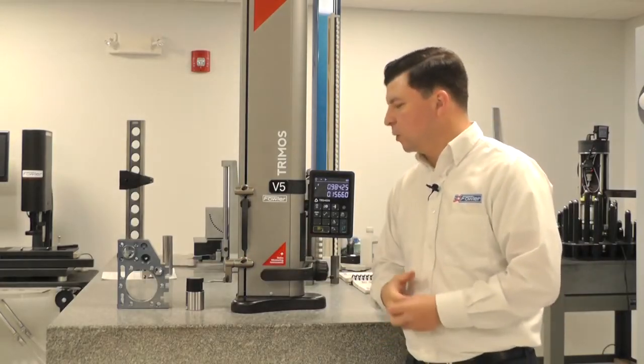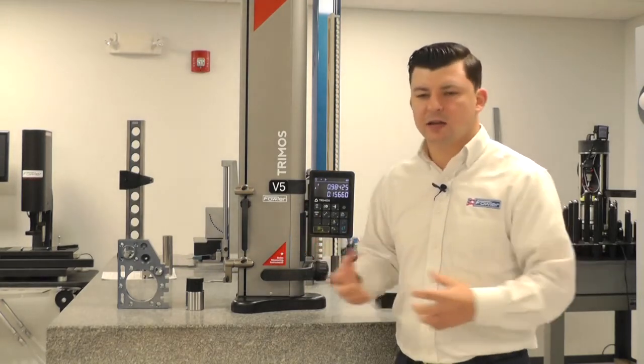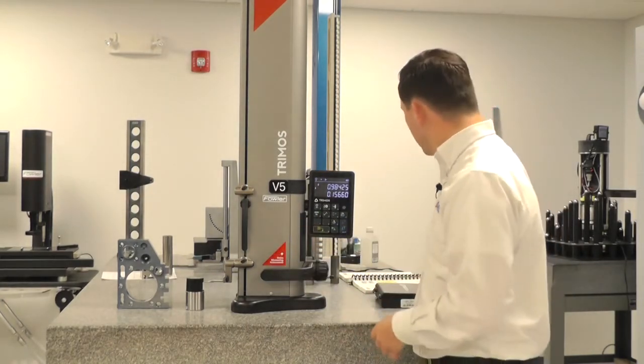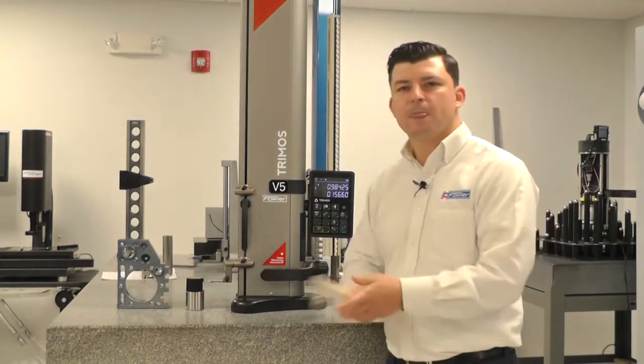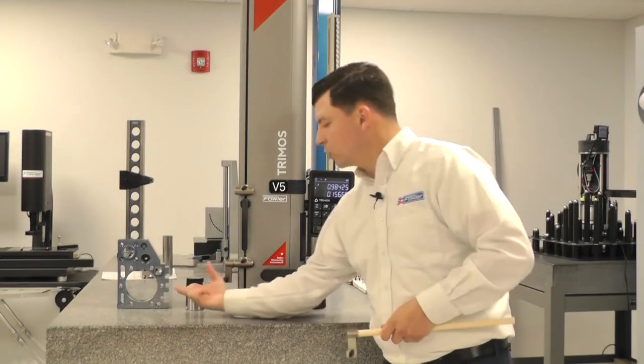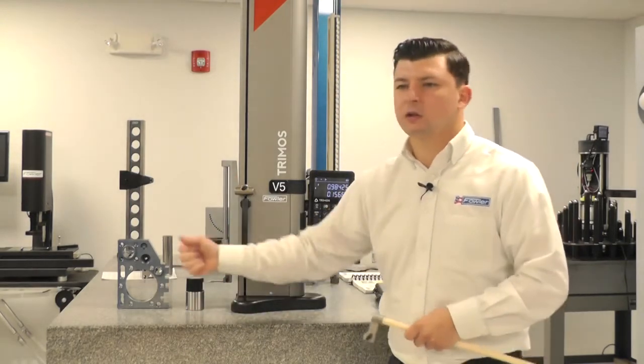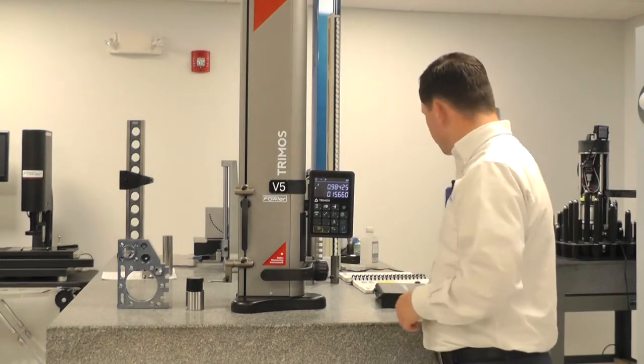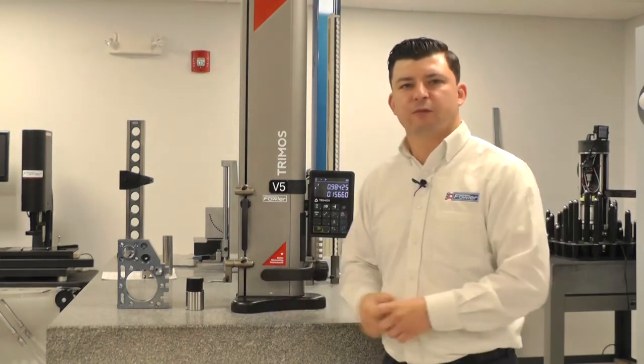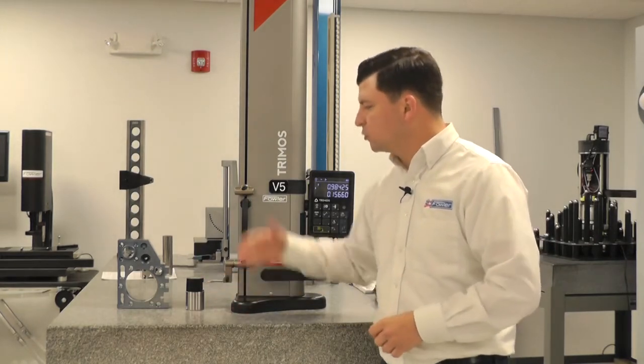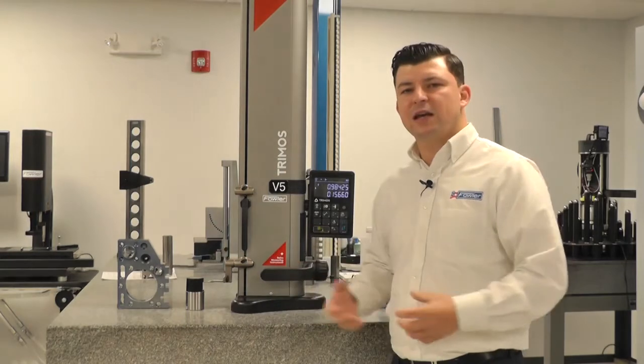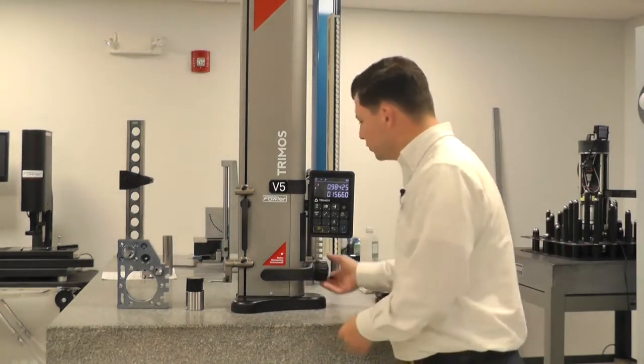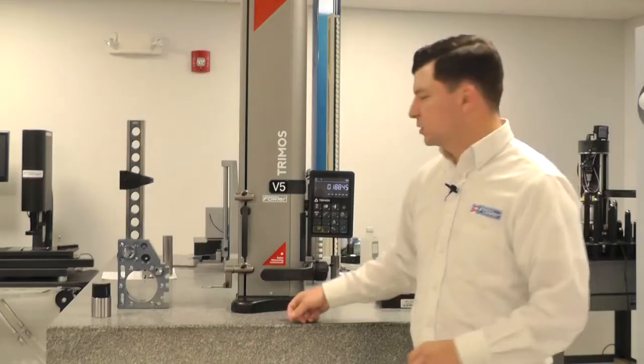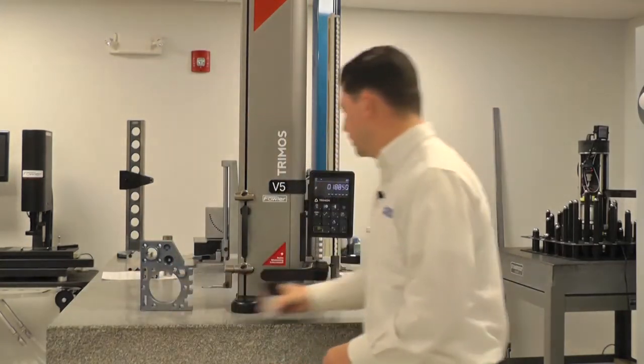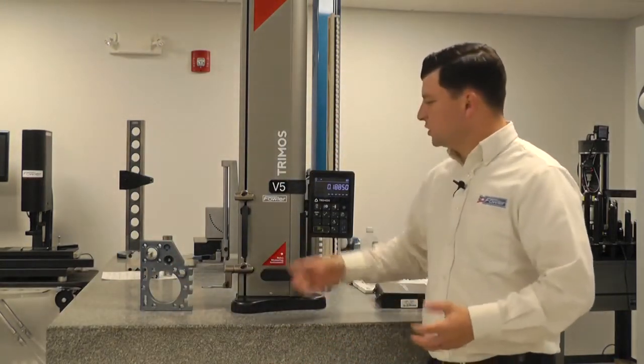When it's taking this measurement, we are actually not only calibrating our probe, but we're also taking into consideration deflection of our probe. So if we have a longer probe, such as our 12-inch extensions, we have probes with a thinner shank, even just a longer straight probe, you're going to see a little bit more deflection the further your probe goes out. But what we're doing is we're calibrating our probe using the same measuring force and the same deflection when we calibrate our probe as we're going to see when we measure our part. And that's how we're going to maintain the accuracy of the gauge. So as we release our contact, that probe icon disappears, and now we're ready to take some measurements. So if I'll bring my demo piece into the display, into the camera here, we'll start to take some measurements.